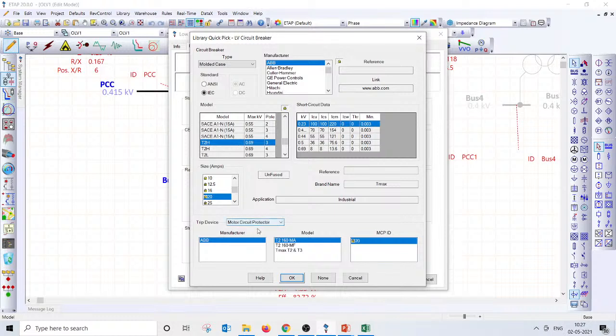So you have a motor circuit breaker also for that, correct? And you need to check the right voltage. I'm sure that is 415 volt. Yep. So you know what is magnetic adjustable, magnetic fixed, right? Thermal, magnetics, all of the stuff. And definitely this needs a bimetallic overload relay as well.